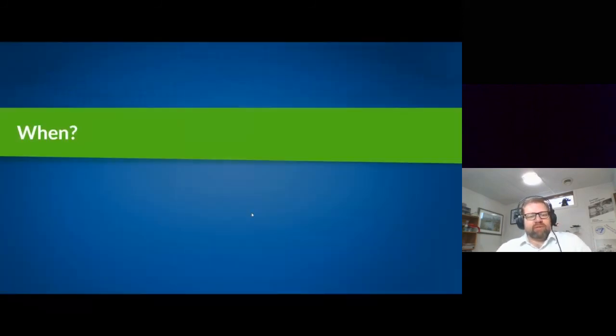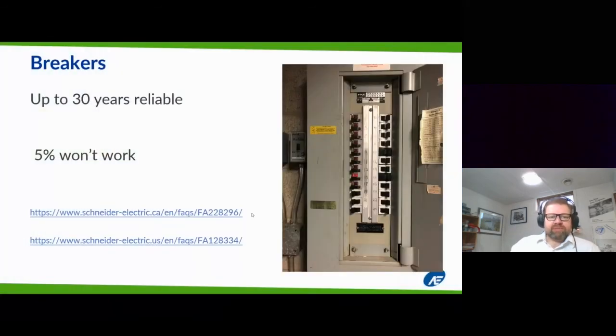So when should you be doing these types of repairs? I brought up the 1980 stimulus money because that's 40 years. Circuit breakers will last reliably up to about 30 years, and then 5% won't work. Eaton's got a white paper on it, Schneider's got a white paper on it, but effectively, if you've got a small building with, say, 500 breakers, about 25 of them probably won't work when you want or need them to.